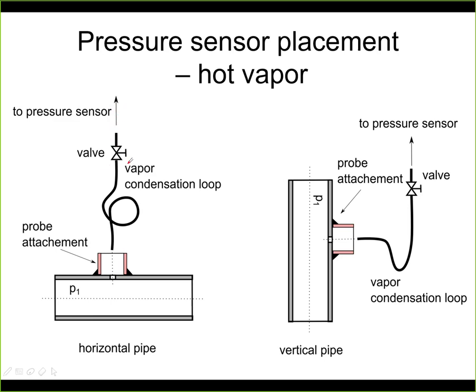So again, here there is a valve, and we might have additional valves in the system, but this valve serves to disconnect again the instrument from this condensation loop and from the probe attachment. It works in the same way also if you have a vertical pipe. So here is the vertical pipe, probe where it's attached. Here is the vapor condensation loop. So here the medium that you measure will cool down, and here we'll have lower temperatures and we may connect the pressure sensor.